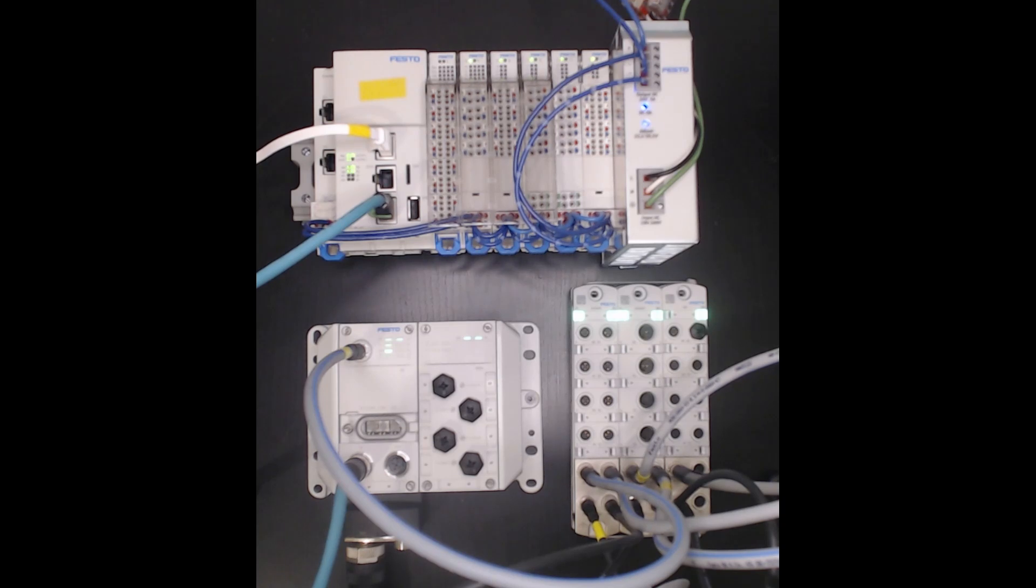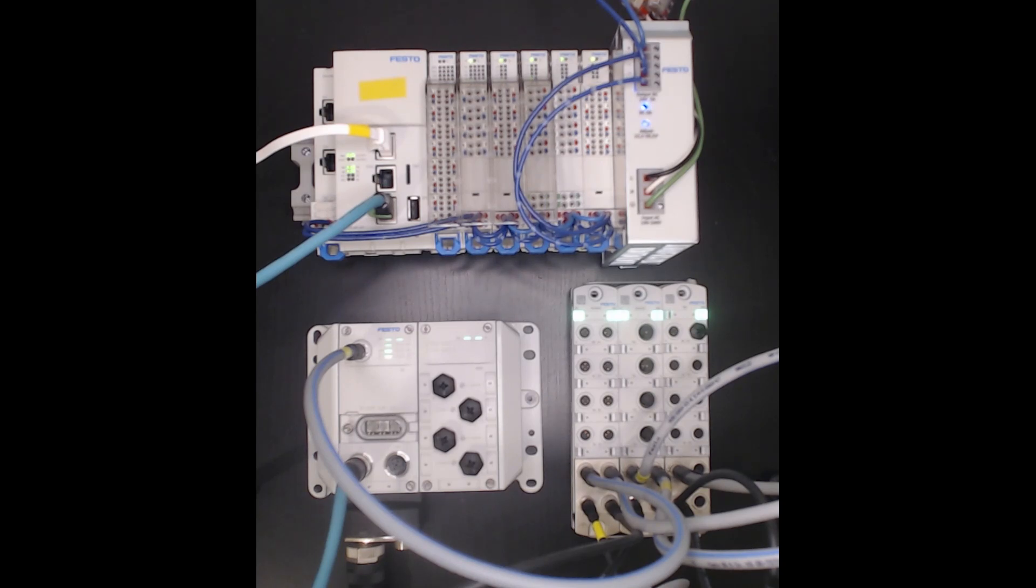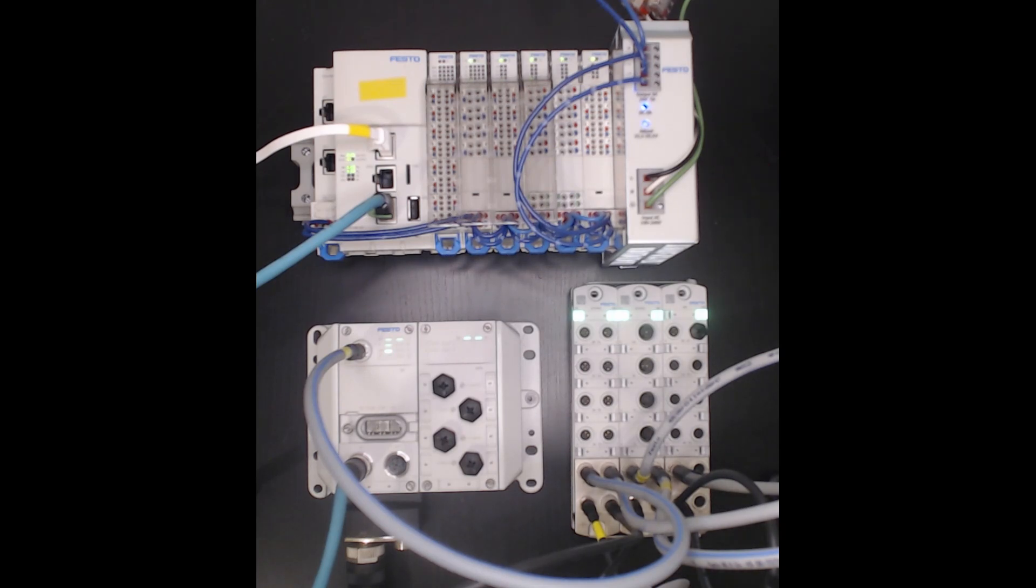And then there are various IO slices for analog and digital IO in and out, as well as a four IO link slice. To the right of that, I have a Festo 120 volt AC single phase power supply. That's the green, white and black wires. And then at the top of the screen, you can see that I'm supplying 24 volt DC out to the rest of all the components.